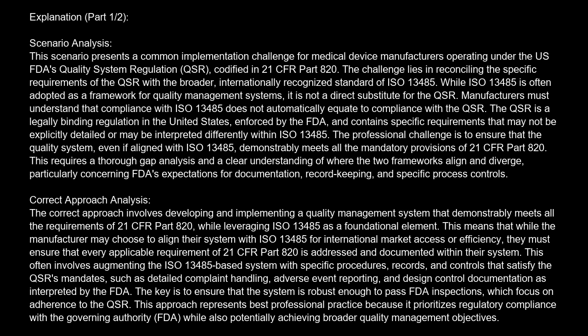Incorrect approaches analysis. One incorrect approach is to assume that full compliance with ISO 13485 automatically satisfies all requirements of 21 CFR Part 820. This is a significant regulatory failure. While there is considerable overlap, ISO 13485 is a voluntary standard, whereas 21 CFR Part 820 is a mandatory regulation.